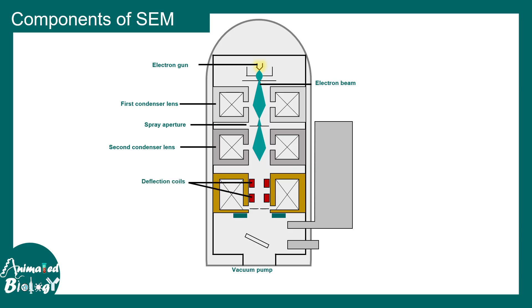The electron beam eventually passes through a deflection coil, which helps in rastering — meaning scanning — the surface topology of the specimen. The objective lenses are shown in yellow. All of these lenses are electromagnetic lenses. To focus an electron beam, electromagnetic lenses must be used. This allows the electron beam to be focused on a narrow volume on the specimen surface and rastered over a desired area.